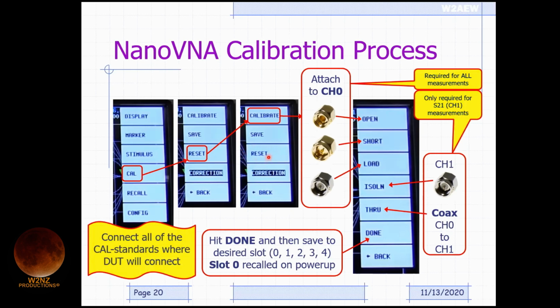Because if the previous calibration was kind of way off when it goes to make the measurement, you might run into some screwy situations. So just a good idea to reset it to start. Versus hitting the calibrate on the middle screen. Yeah, rather than going right to here and hitting calibrate, just hit reset once and then go to calibrate. When you hit reset, you'll see those indicators on the left side disappear. And then you know you're starting clean, and then hit calibrate. Thank you. Okay. Hey, Alan, a quick question here.